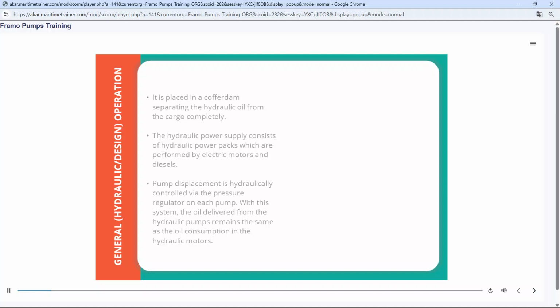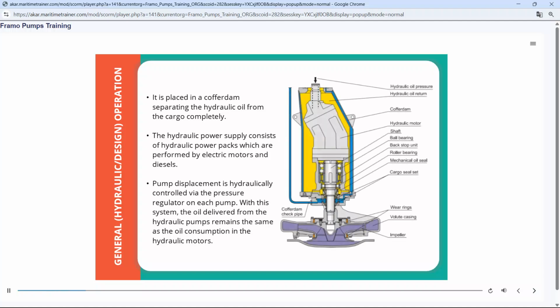It is placed in a cofferdam, separating the hydraulic oil from the cargo completely. The hydraulic power supply consists of hydraulic power packs which are driven by electric motors and diesels. Pump displacement is hydraulically controlled via the pressure regulator on each pump. With this system, the oil delivered from the hydraulic pumps remains the same as the oil consumption in the hydraulic motors.